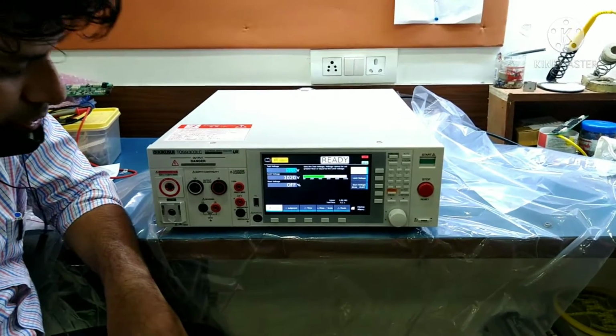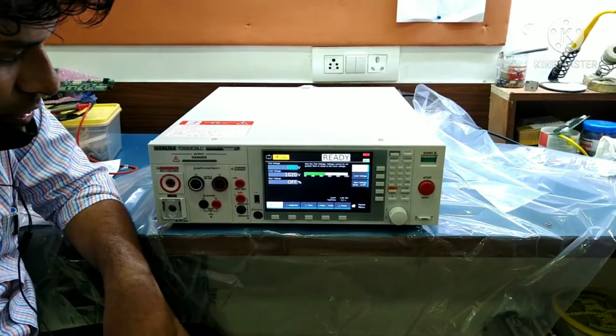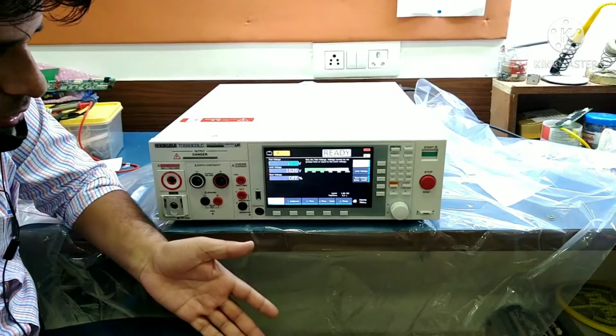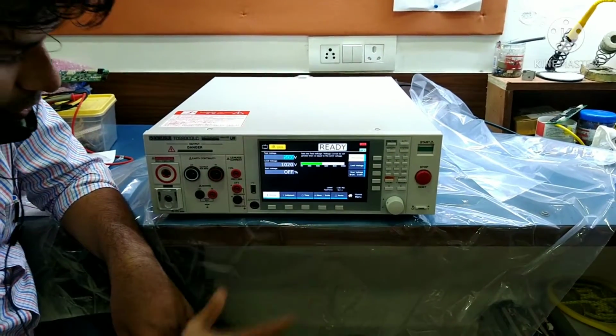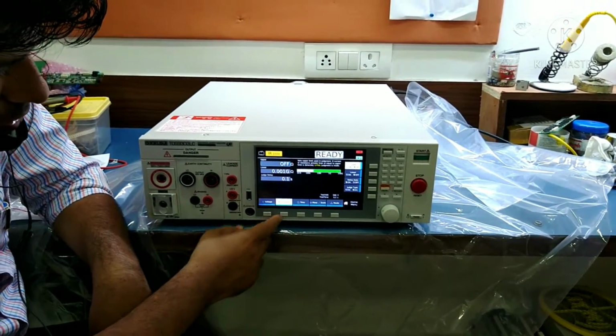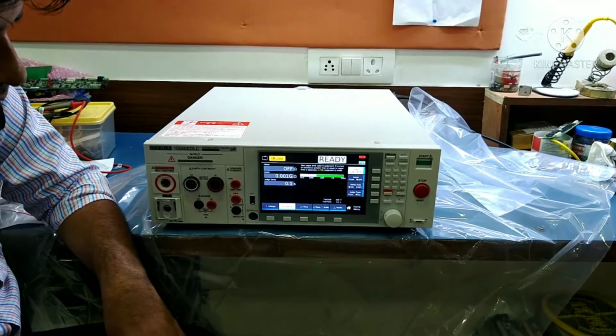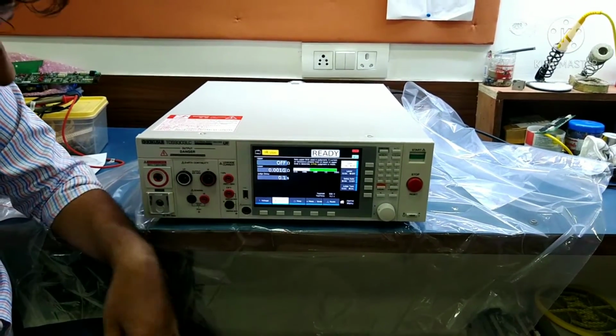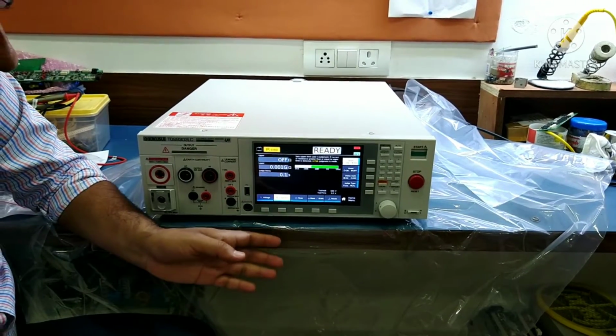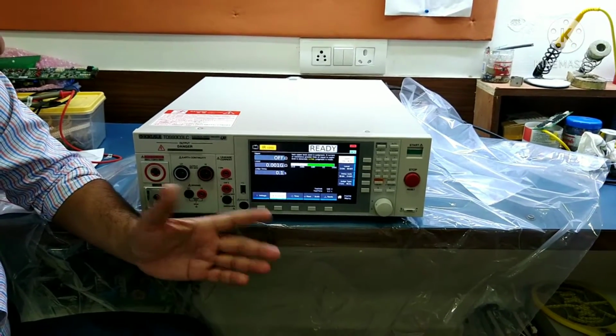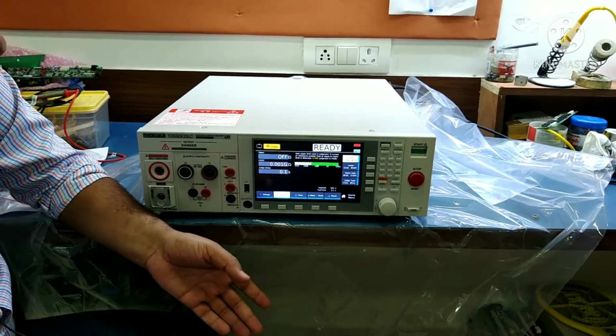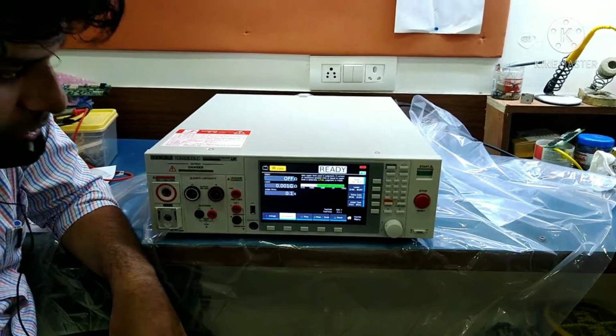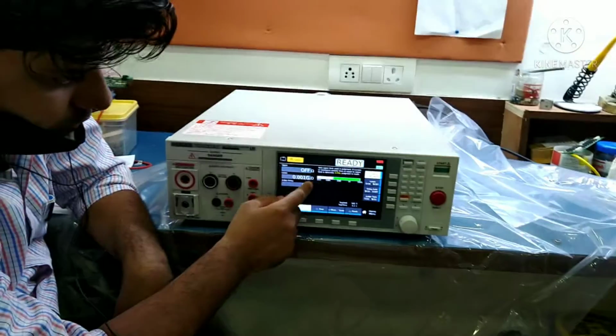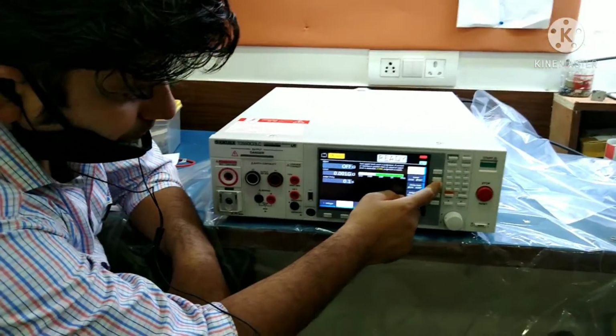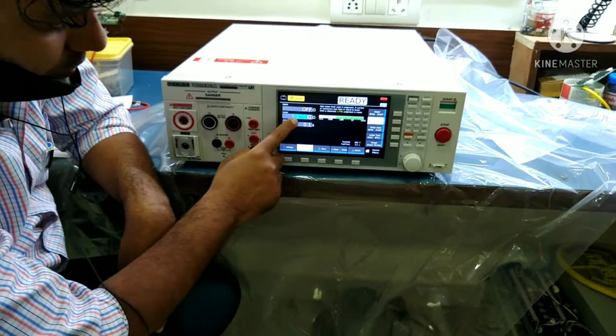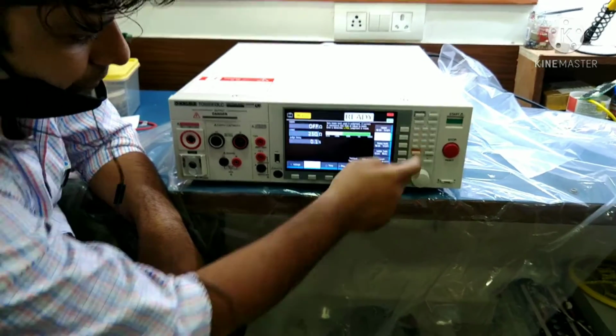We don't need to disturb the maximum capacity. This is also the start voltage, so what voltage you want to start. So we will make it off. This is the judgment. Judgment in the sense of the insulation, we are setting the resistance value. For any device, if it resists more than that, it is a very good quality of that product in the case of the insulation. So we are going to set the lower setting. Lower. So I'm going to set 25 mega ohm.